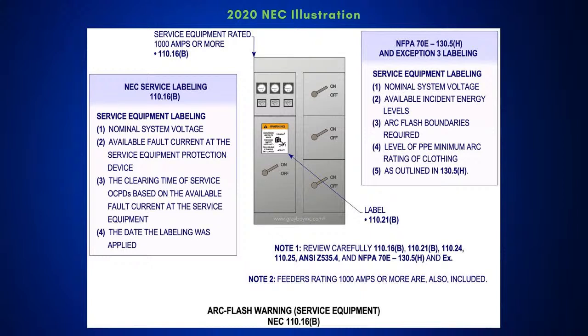Now, when this first came out, and you've heard me say this before, I was on the task group when we did all this. We put the tables together for selecting your PPE, depending on the type of equipment you were working on in the task and setting up the parameters and all that good stuff. Well, one of the things that we do in our publication is to let you know why something happened. When we put that table together, we were having problems because we did it for the contractors that go out. They didn't have a staff and they needed...